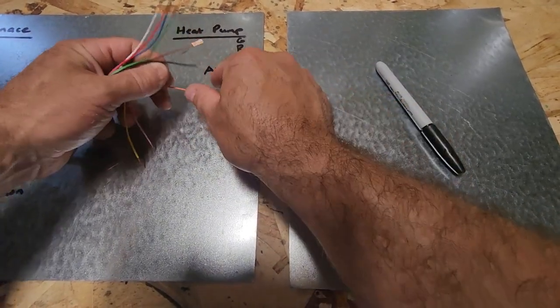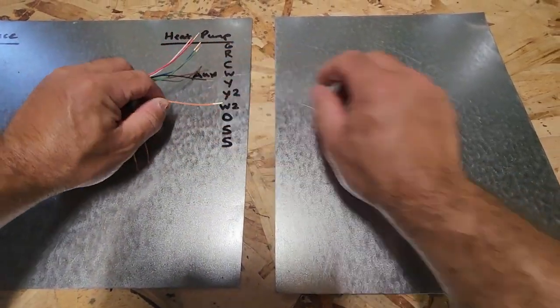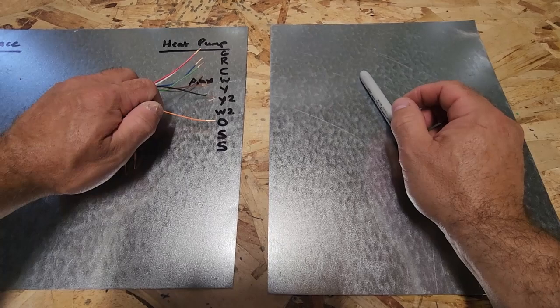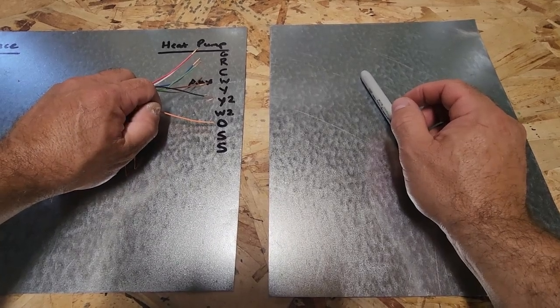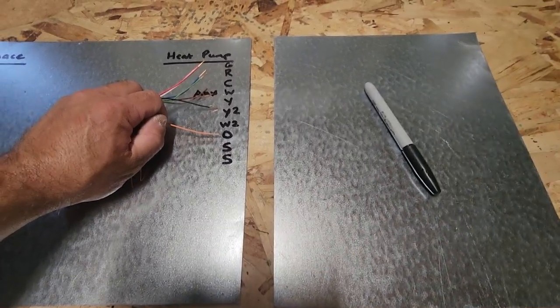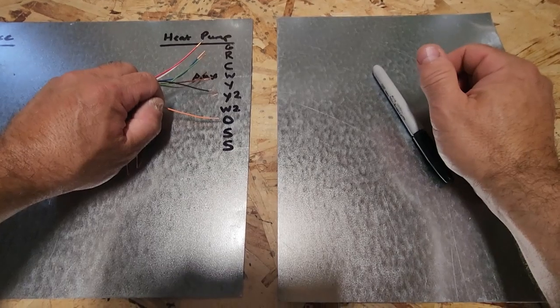So that's going to be your orange wire here, okay? Always use orange. That's for your reversing valve, or what some people call a switchover valve. That's what switches your heat pump between heating and cooling.